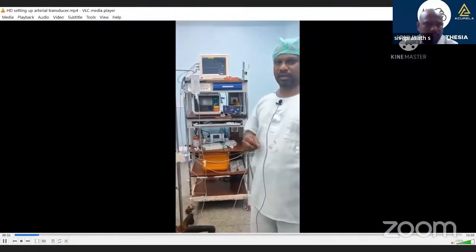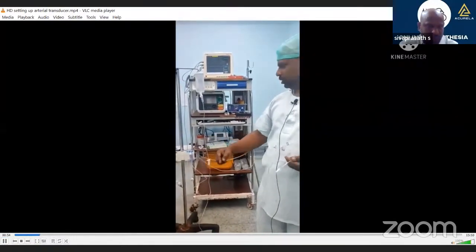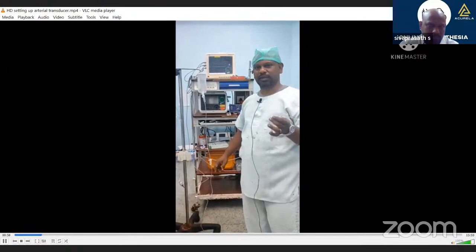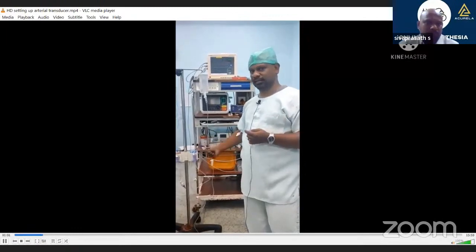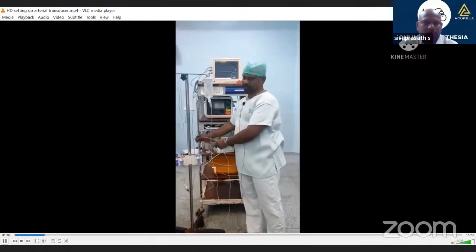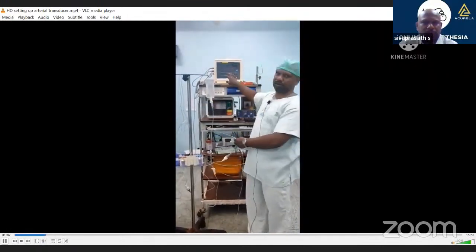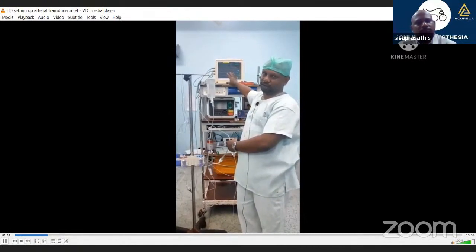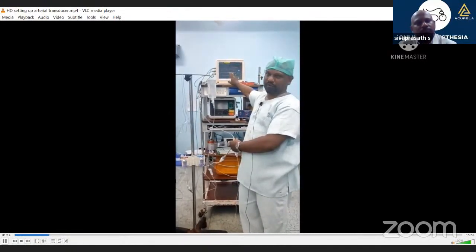So what are the components of such an invasive pressure monitoring system? We have three components. First is a rigid pressure tubing that conducts the mechanical energy from the patient to the transducer. Next is the transducer, which converts this mechanical signal into an electrical signal at this interface, and an electrical system, the wire. It conducts the electrical signals to the monitor. This monitor filters it, evens out the waves that are produced here, and shows a numerical value as well as a waveform pattern.